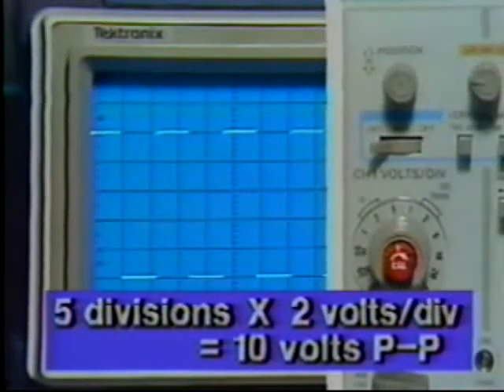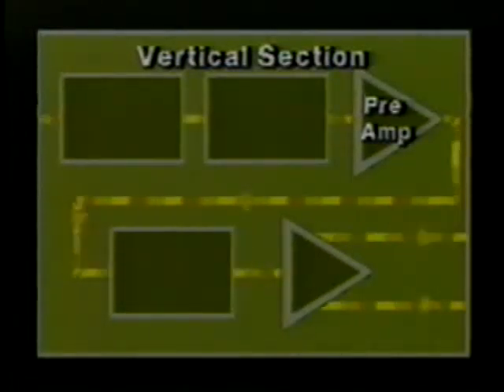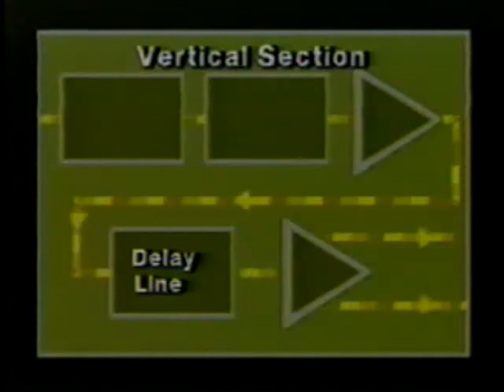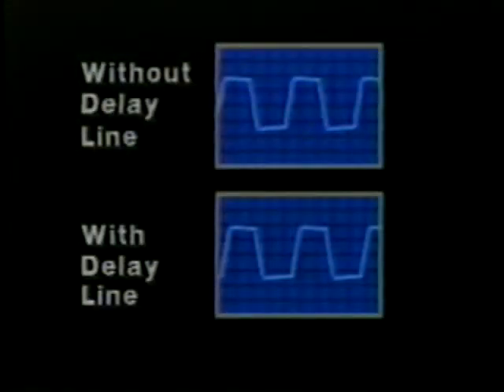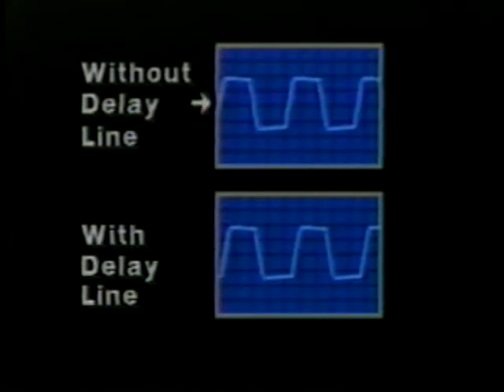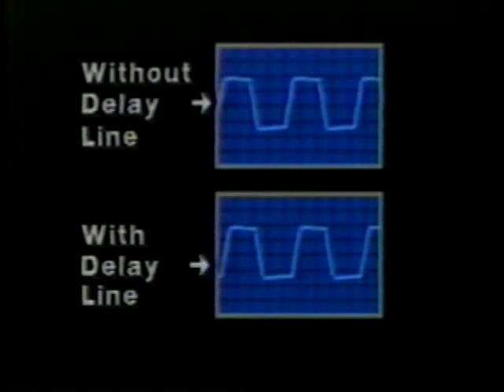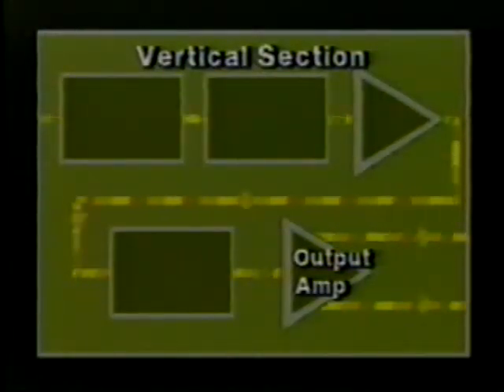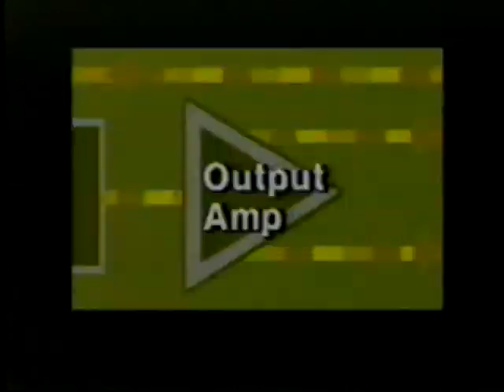Following the vertical input amplifier, the next block the incoming signal encounters is the delay line. This line delays the signal output from the vertical input amplifier for a short period of time so the horizontal sweep generator circuitry has time to initiate a sweep before the vertical signal reaches the CRT vertical deflection plates. This coordination of vertical and horizontal timing by the delay line lets us view the signal's leading edge — without delay the signal would look distorted, but with delay it appears correctly.